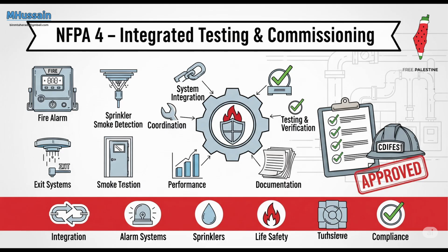Precisely. And this documentation needs to be kept safe. The property or building owner is the one responsible for record retention. For how long? The initial integrated system test documentation, that very first report, must be retained basically for the life of the system, or at least until a completely new initial report is generated, like after a massive overhaul. For the periodic tests, the standard typically requires keeping the two most recent reports or test documents. Yeah, you always have a recent history. Right. And all these records have to be kept together in one specific location in the building. And that location should be clearly identified, usually right at the main fire alarm control unit, so anyone who needs it, maintenance, inspectors, fire department, knows exactly where to find it. That makes sense. Easy access.